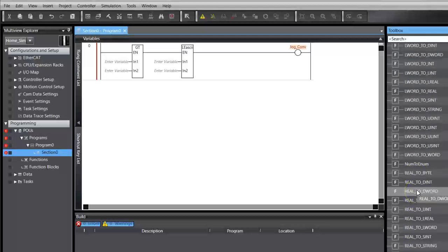So this works sometimes when you get an input that you have to use, but you want to convert it to integer, but it comes in as a real number. Analog inputs use real. But if you just want to use that in some program that's already set up to use integers, you could do a conversion, convert real to integer. Typically what that does, it truncates all the decimal points off. But there are some mathematical conversions that will happen there too.